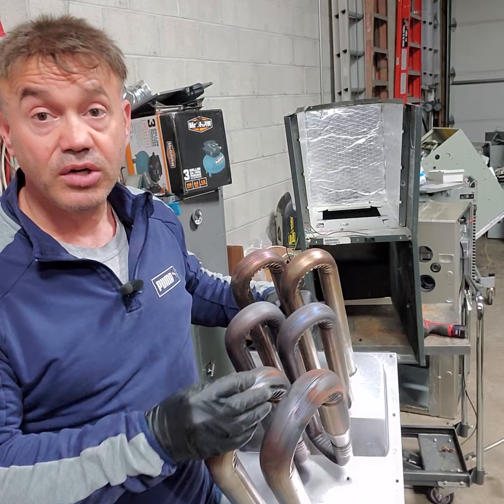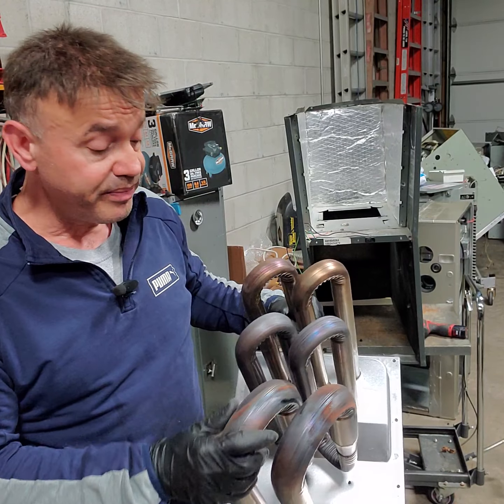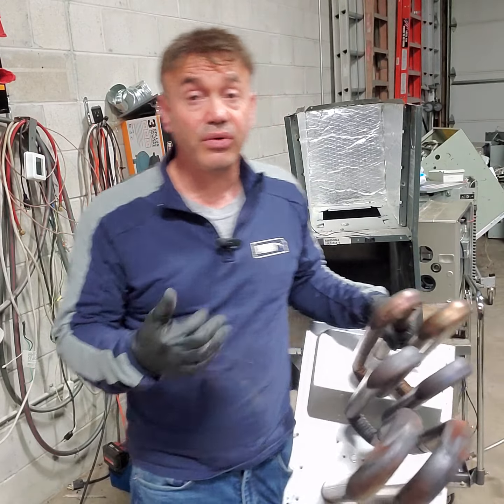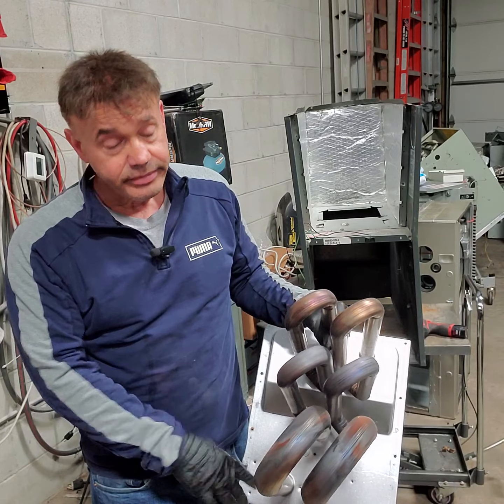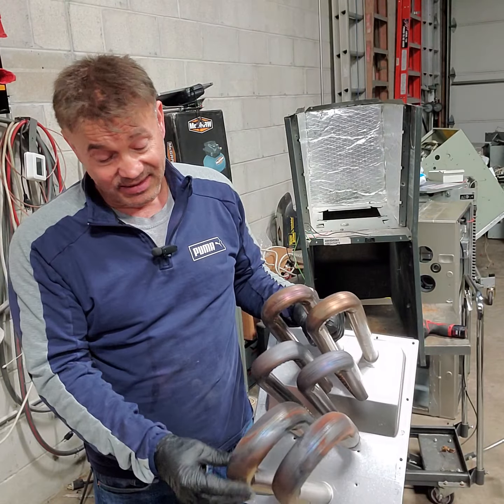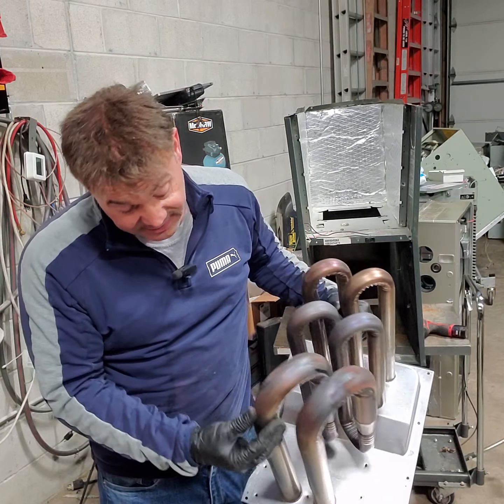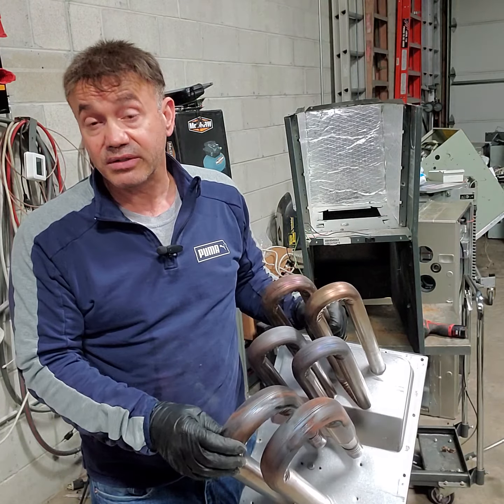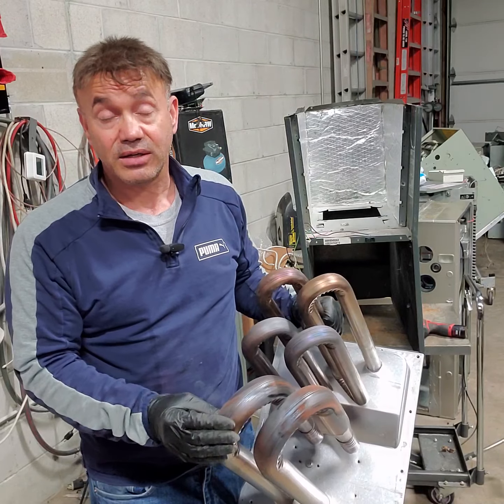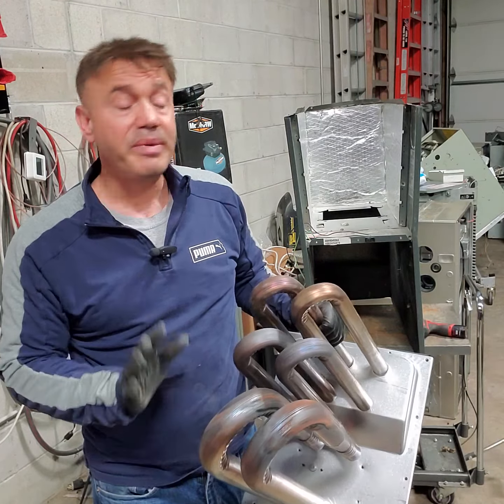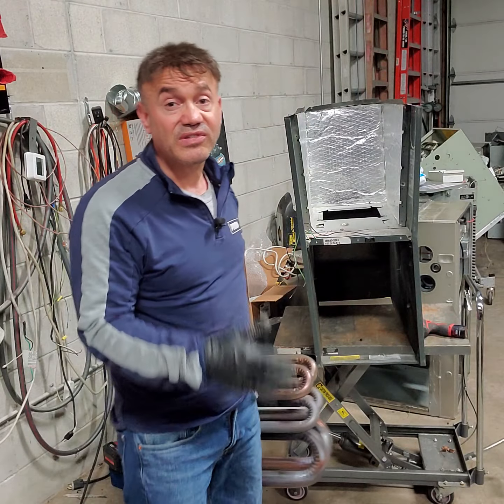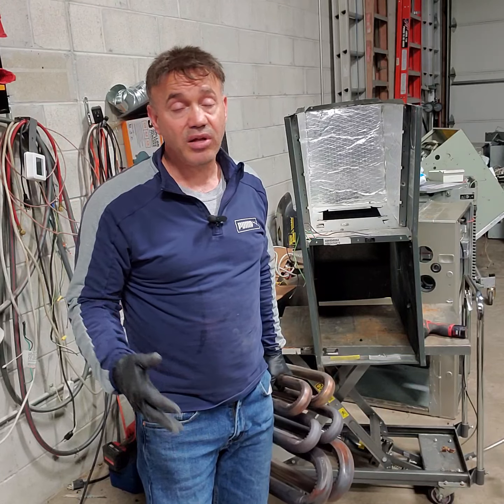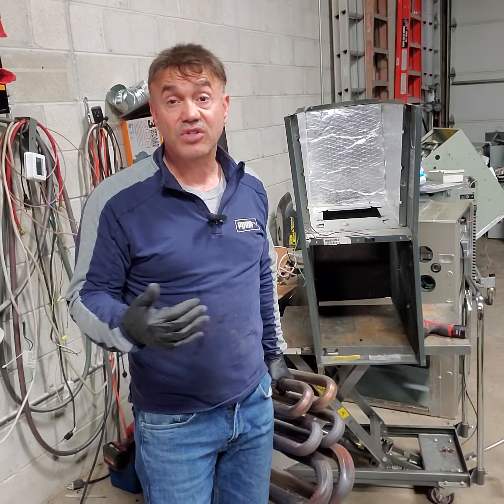But as you see, I tell my customers always, looks like the gas valve was set really strong, nobody adjusted it. When it's really, really cold and the furnace works longer hours, no matter how much air you have coming in, this can really overheat. If you could see it running, it becomes kind of orange. Again, it's all because the person or company who installed the furnace did not send a startup team.